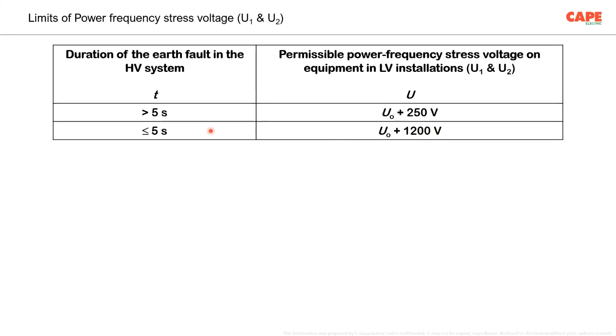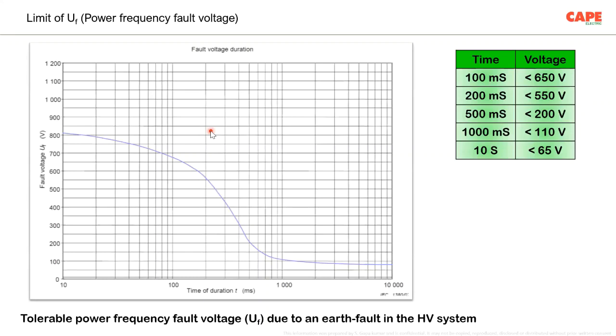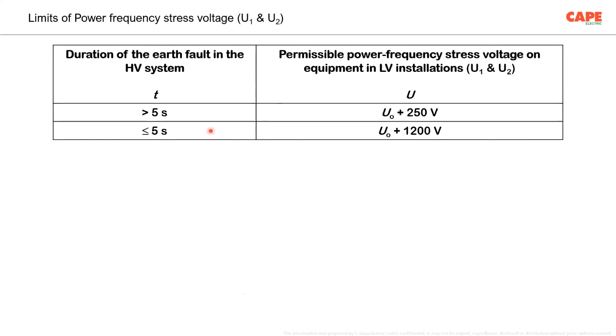So two points. One is the shock voltage, as I showed you in this particular picture. I'm sure you are able to see the limit of the power frequency fault voltage. It means the shock voltage limit. Number two, the stress on the equipment also has to be limited to almost this much level. It also means your equipment is able to withstand, say for example, up to 5 seconds, 1200 volt. When you buy an equipment, when you know that your equipment can withstand only 1200 volt plus 230 volt for up to 5 seconds, you must ensure that the voltage going into your electrical appliance, due to various reasons, is limited to a level less than this. Otherwise, your equipment may fail.